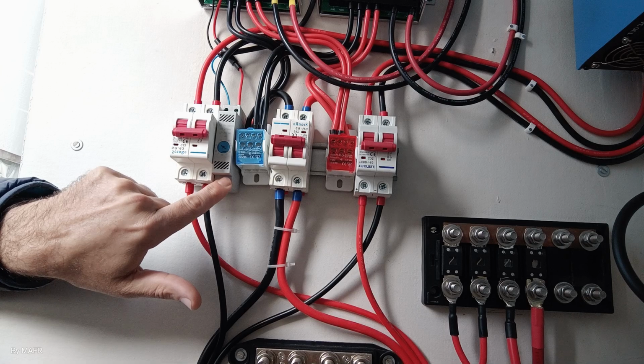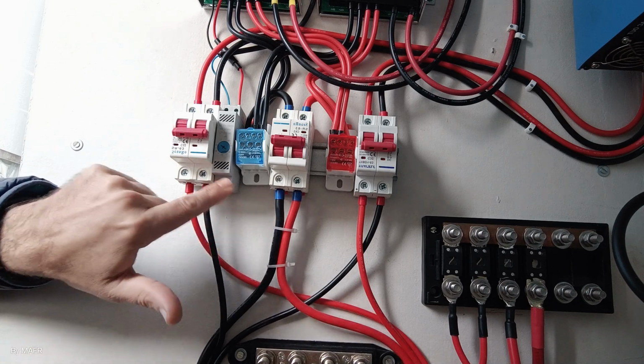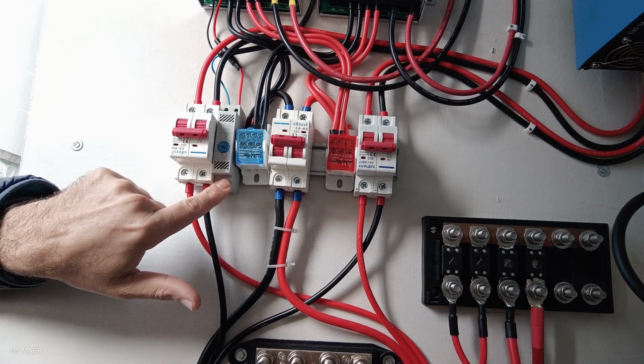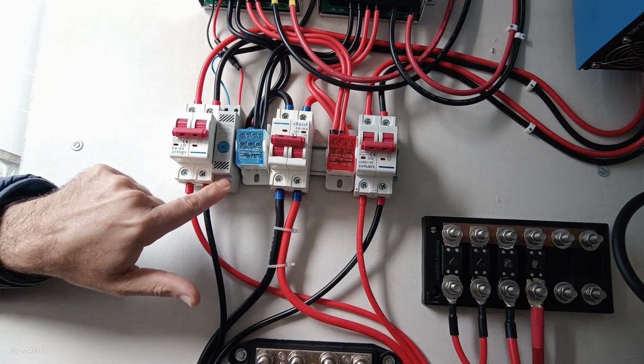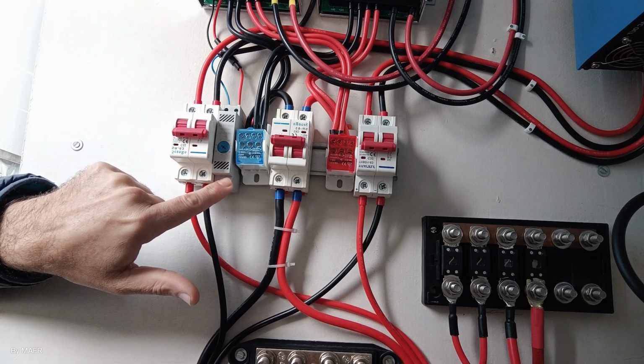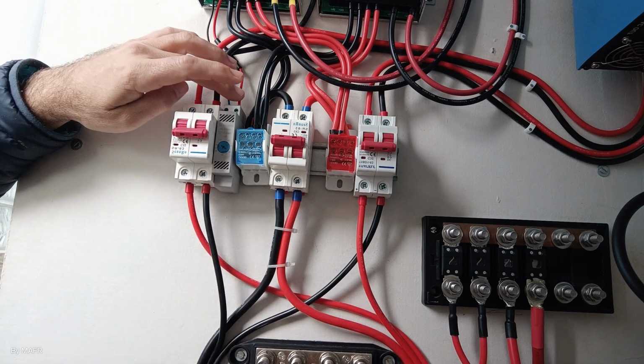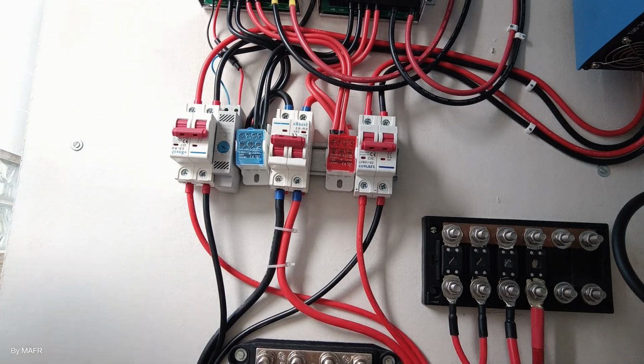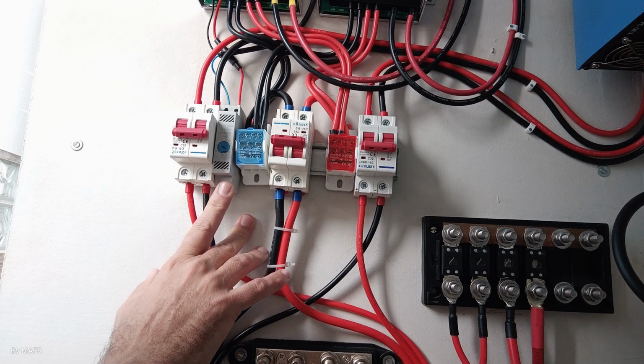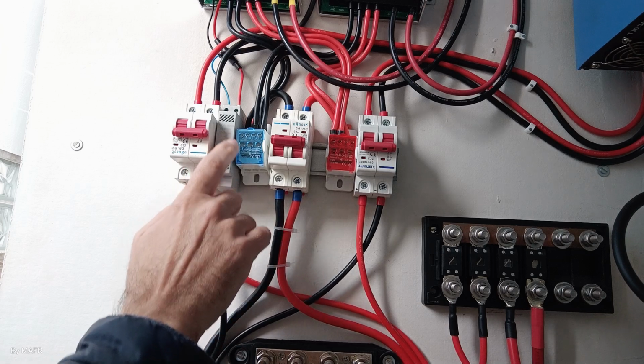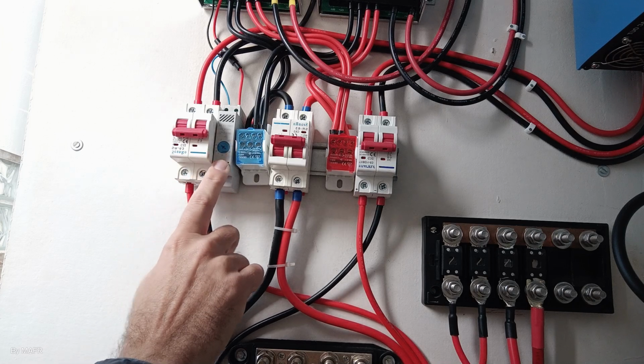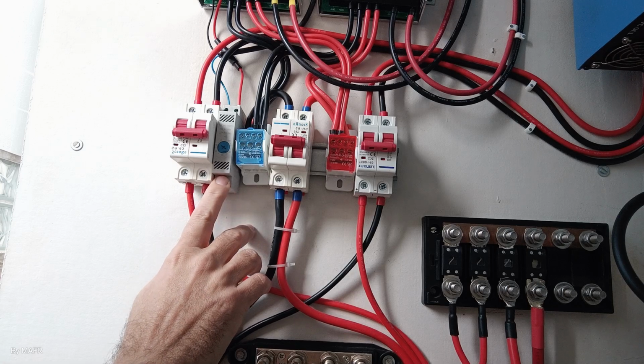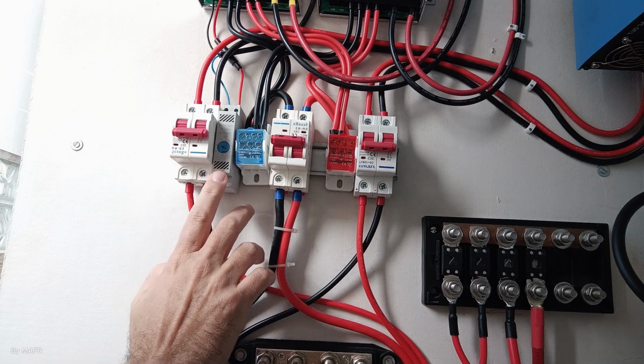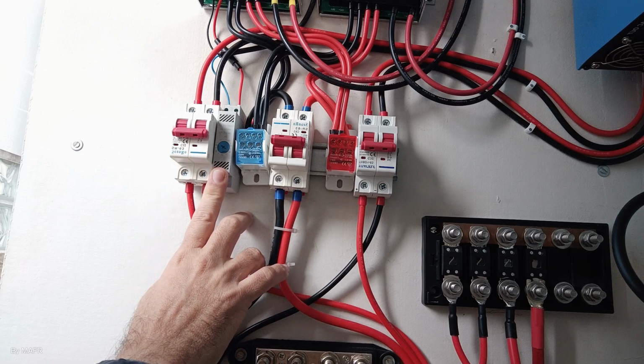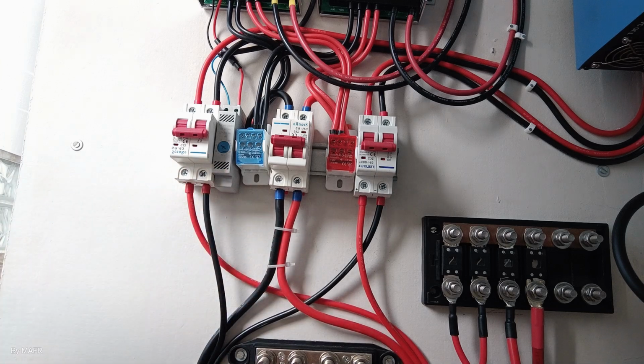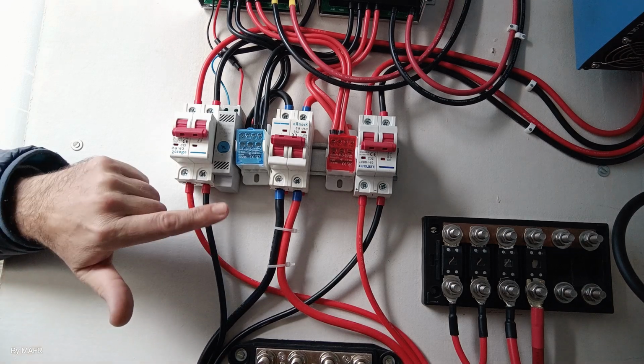And the last one is the thermostat. As this is in a rack, not in an open space, I have a thermostat which works from 0 to 72 volts DC, and it's connected to the charge controller, right? When the rack is above 25 degrees, and you can configure the temperature here, you can put 20, 25, 30, 40, whatever you want, it will turn on the fans automatically. So basically it's fully automated. You don't need to do anything when it's in operation.